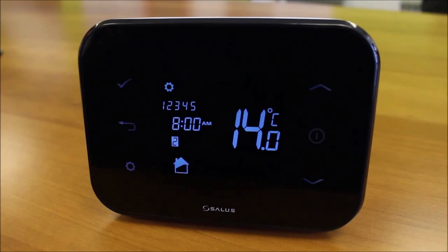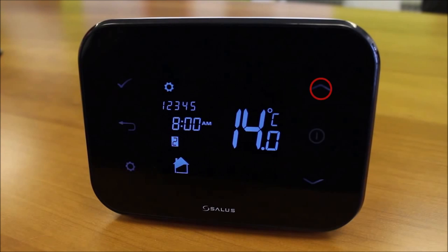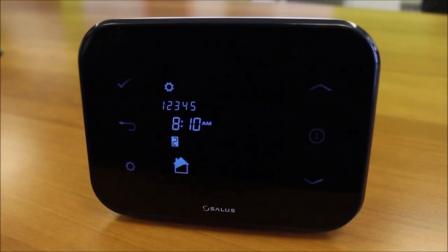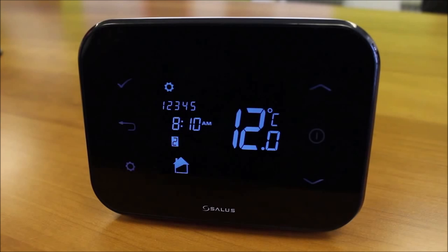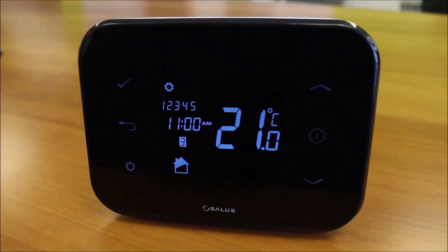Programming 2: use the UP or DOWN arrow key to change the hour. Press Tick to confirm. The minutes will now flash. Use the UP and DOWN arrow key to change and press the Tick to confirm. You will notice we are dropping the temperature. This would act as an OFF period because the room has to drop below what you program in. Please repeat the process on the remaining four programs.